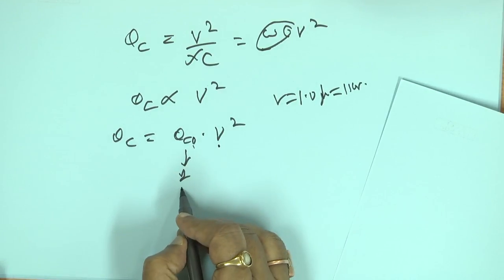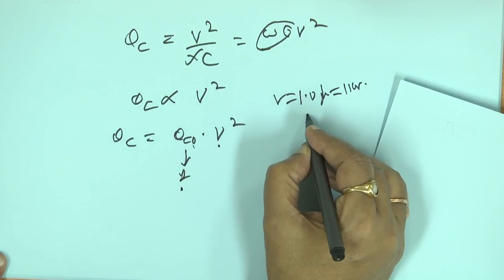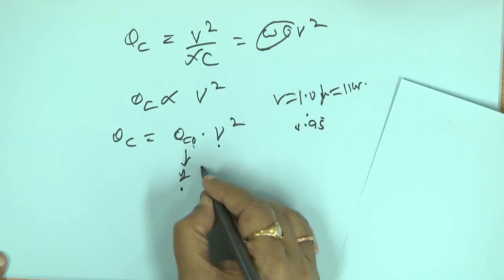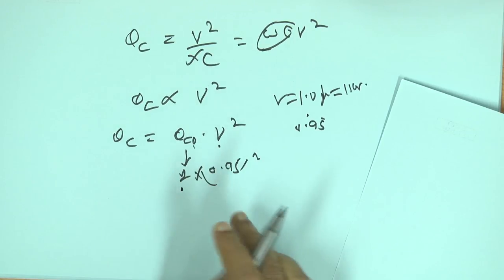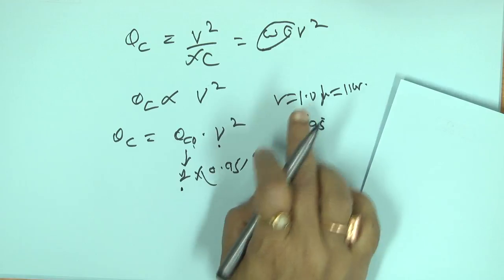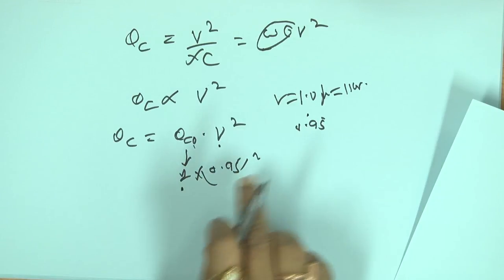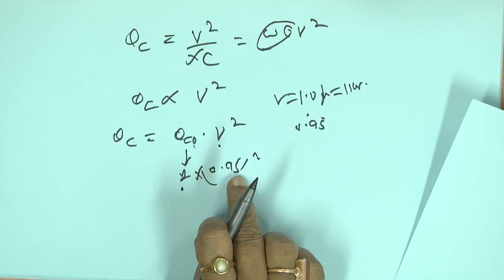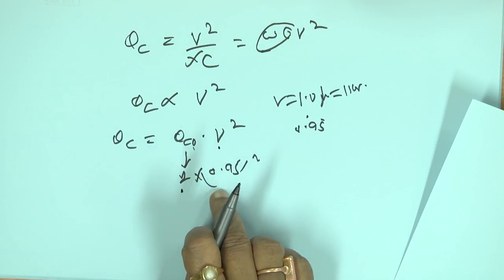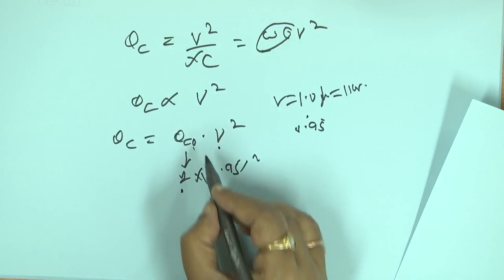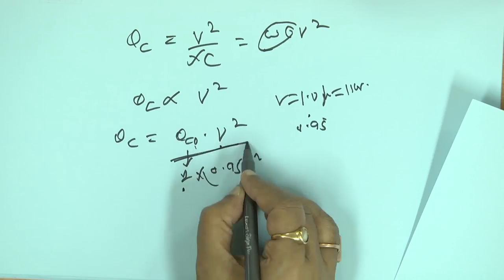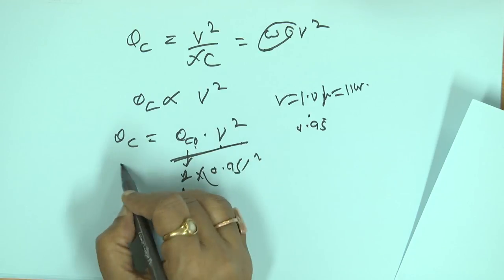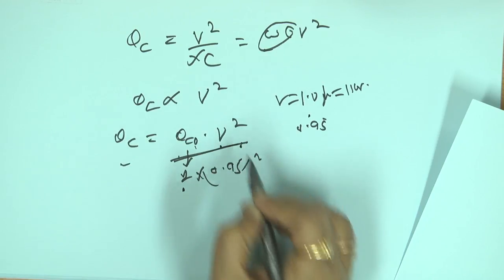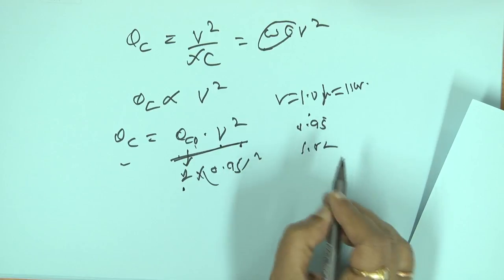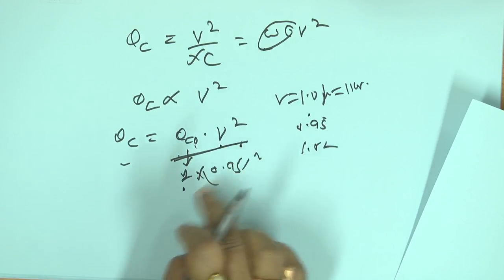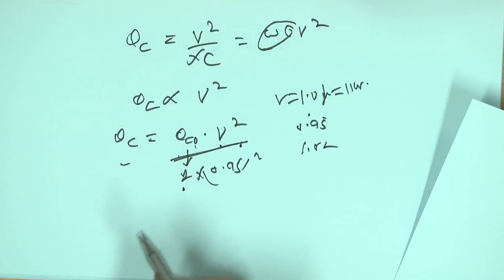Then it will inject 1 megavar. But the question is, if voltage is less, suppose it is 0.95, it will be 1 into 0.95 square, right? So it will be less than the specified rating. Generally you will find most of the voltages are less than the rated voltage, so it will inject less reactive power. That means whenever somebody is doing research, they need to consider this capacitor as a constant impedance load. But if it is more than that, say 1.02, then it will be 1.02 square, so it will inject more than the rated one.